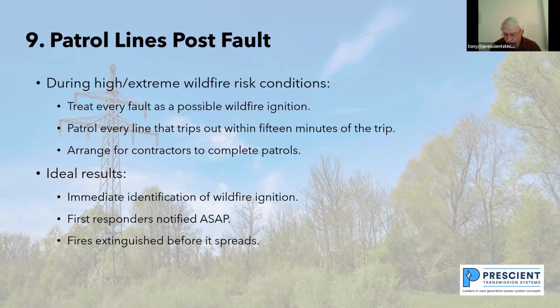and Uber drivers to go out and patrol the line within 15 minutes of a trip out. On a distribution line, you're saying, well, the high wildfire risk is going to be maybe 7 days a year. And what's it going to cost you to get people trained to patrol your lines? Well, you're not going to train people to go out and actually do any restorations. They're just going out looking for a tree down or something like that and calling back saying they either didn't see a fire or they did see a fire.